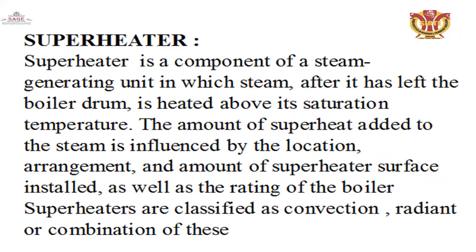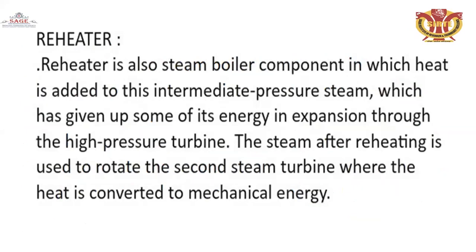The superheater is a component of a steam generating unit in which the steam, after it has left the boiler drum, is heated above its saturation temperature. The amount of superheat added to the steam is influenced by the location, arrangement, and amount of superheater surface installed, as well as the rating of the boiler. It may be of convection type, radiation type, or a combination of both.